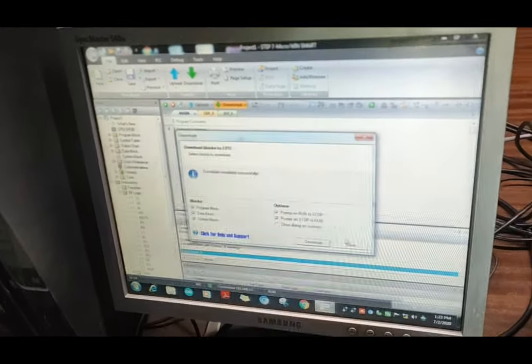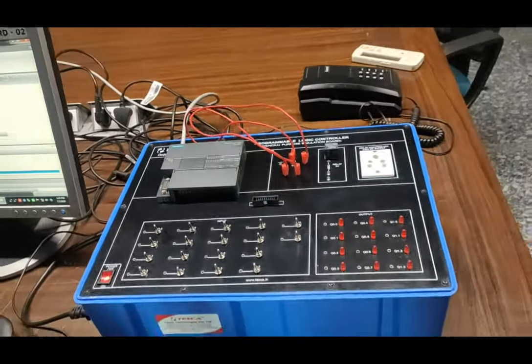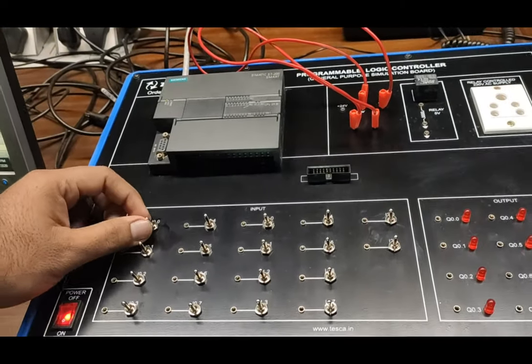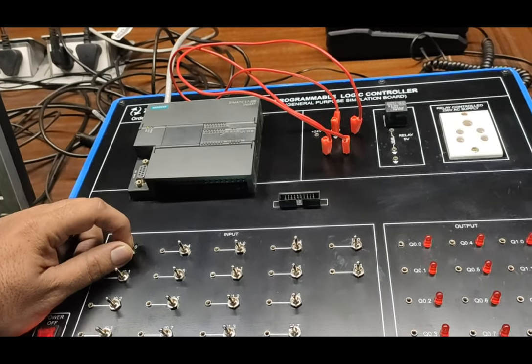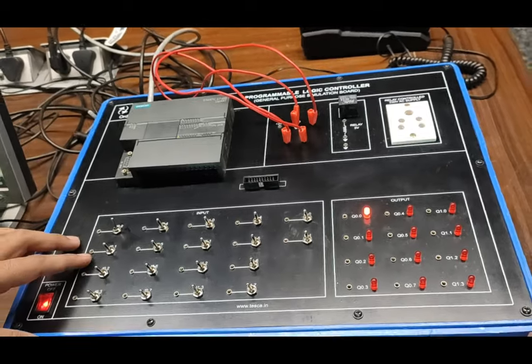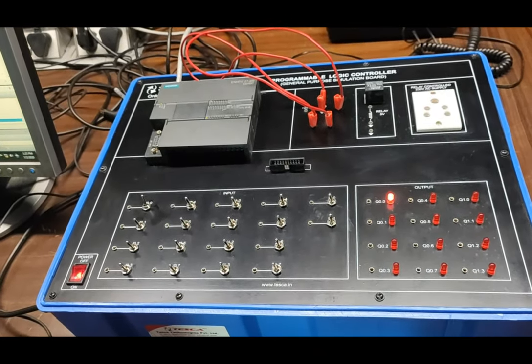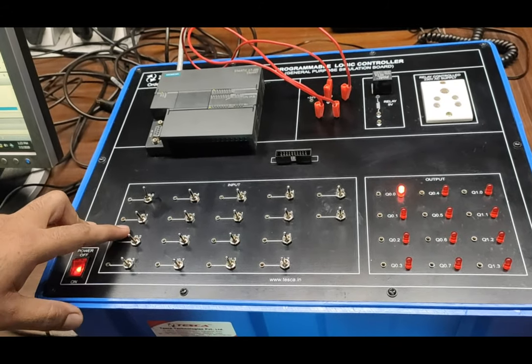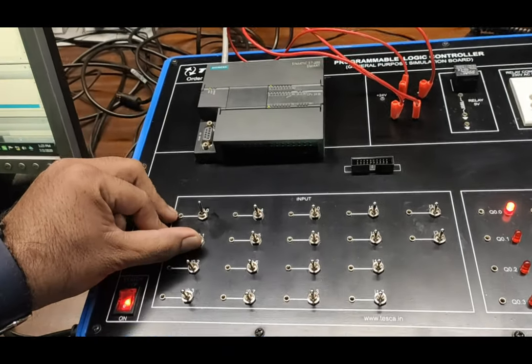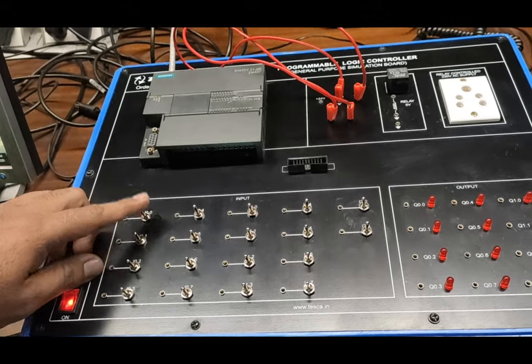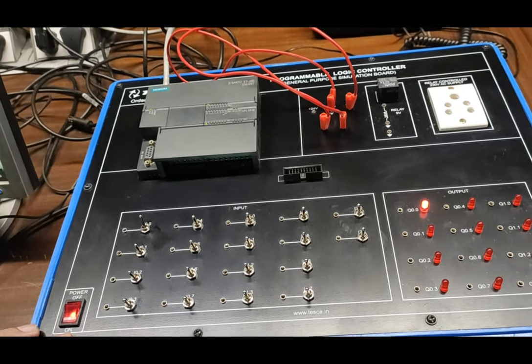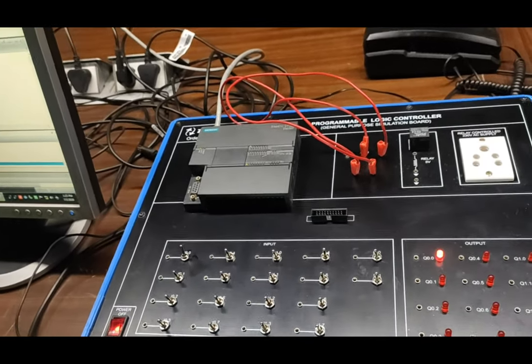The programming is done. We download this program and start the simulation. At the kit, as input 0 is toggled again and again to reach 5 counts, after 5 counts the output will come on. As the preset value reaches 5 counts, the output goes ON. For resetting the counts, we have given input 1 in the program. As we press input 1 ON, the counter resets. When we give input 5 times to the PLC, the counter's process value will be processed and the output will occur after 5 presses.